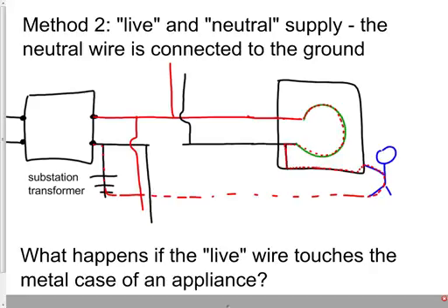Now if we follow the same argument as before, but instead of connecting the neutral wire to the case, we connect the earth wire to the case, it still provides us the protection we had before. If the live wire comes into contact with the metal case, current can flow through the earth wire, through the ground, back to the substation, hopefully blowing the fuse in the appliance and rendering it safe.